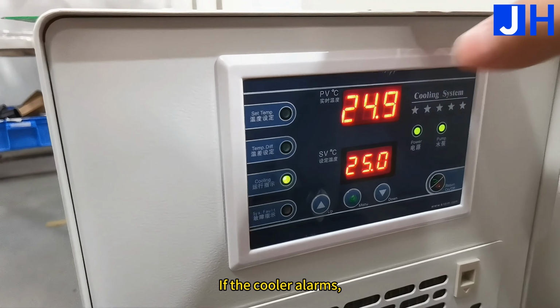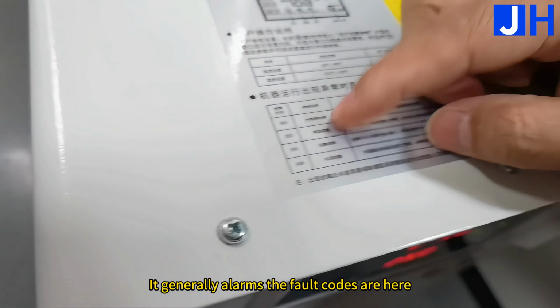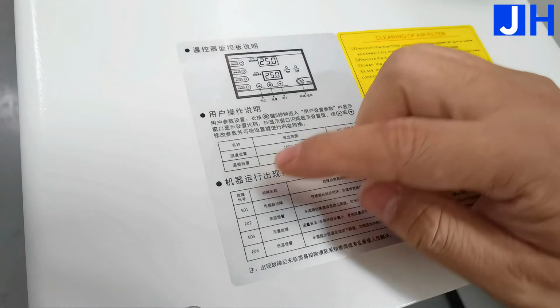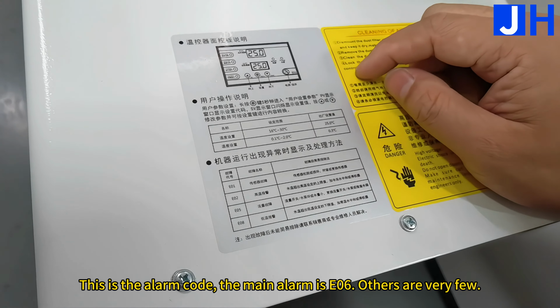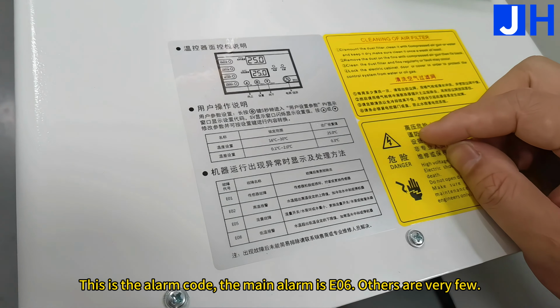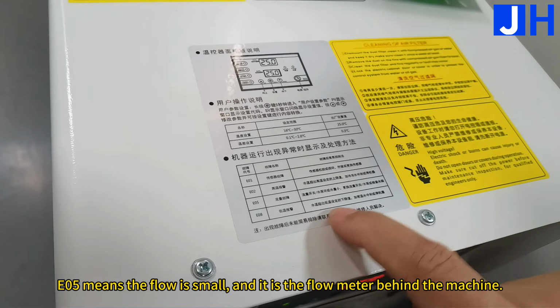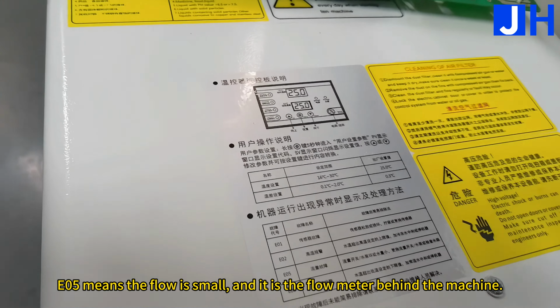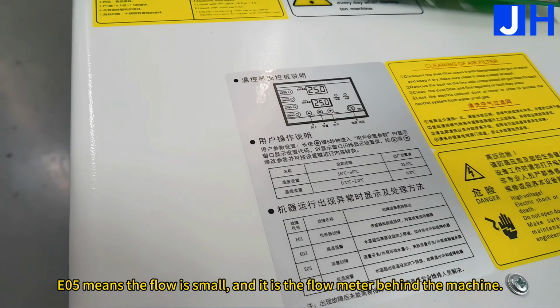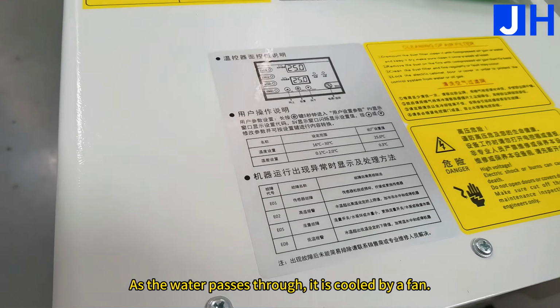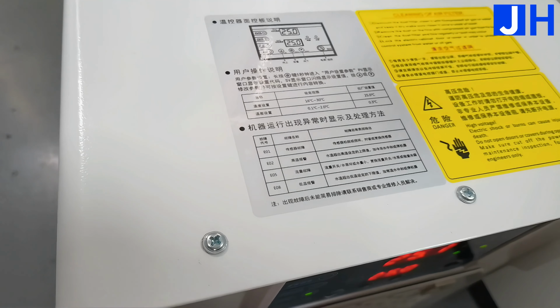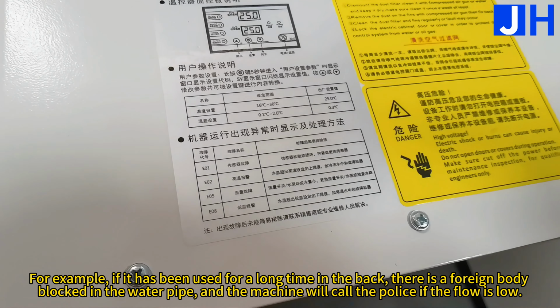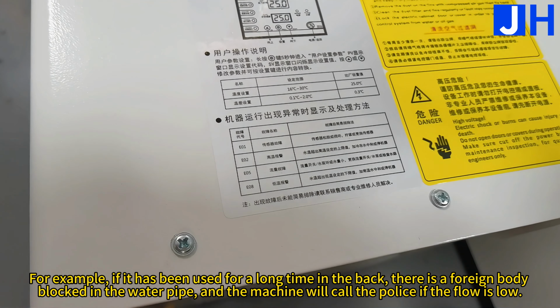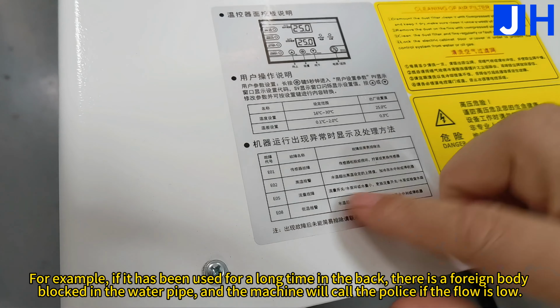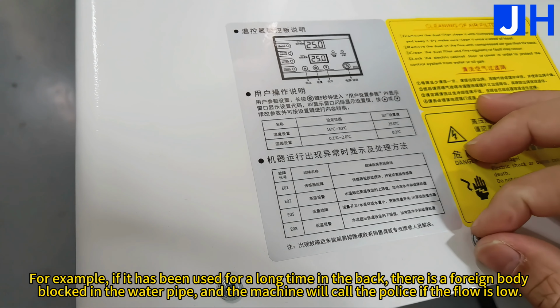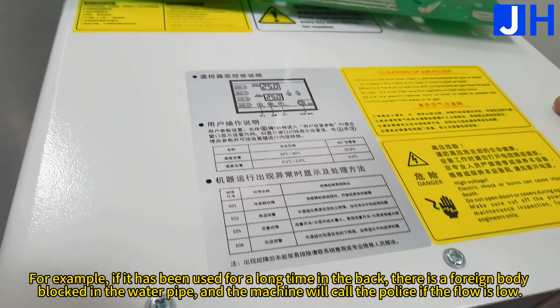If the cooler alarms, the fault codes are shown here. This is the alarm code. The main alarm is E06. Others are very few. E05 means the flow is small, and it is the flow meter behind the machine. As the water passes through, it is cooled by a fan. For example, if it has been used for a long time, a foreign body may block the water pipe at the back, and the machine will alarm if the flow is low.